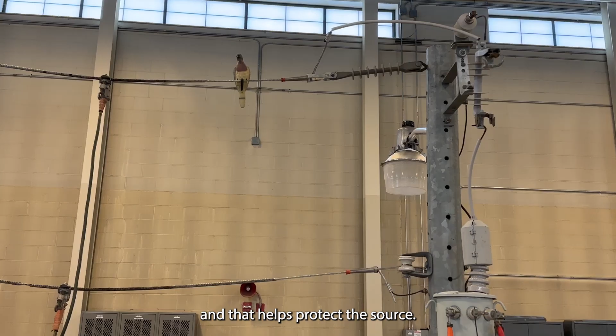Next, above our transformer, you're going to see what we call our fused cutout. This door here is the fuse, and when closed, will allow the electricity to flow into our transformer. If there is a problem down here somewhere on the transformer side of things, our fuse will blow, and that helps protect the source - the source being our power line out here.